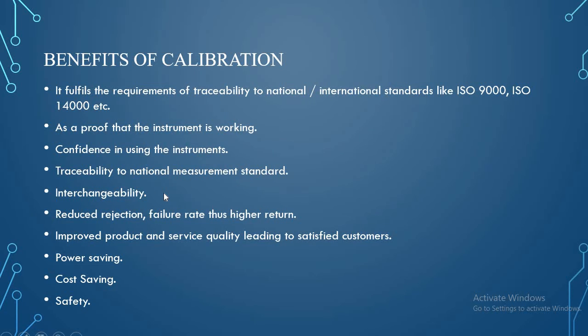Then interchangeability, that is also one of the benefits of the calibration. Then next one is reduced rejection, failure rate, thus higher return. So when we get accurate results, and the readings are not up to the mark, we can go for the corrective action. So by taking the measurements from time to time with calibrated instruments, we can reduce the rejection so that the failure rate can be reduced, and so the benefit will be more. The next benefit is improved product and service quality leading to satisfied customers. Also power saving and cost saving, and one of the most important benefits is the safety. When an instrument is calibrated, it also assures the safety of the operating person.